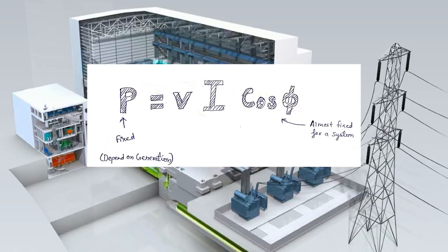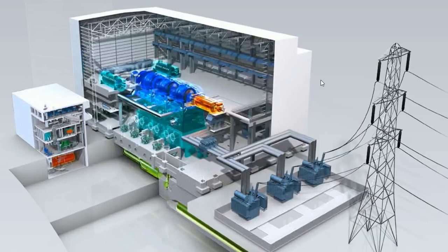Obviously the best choice is higher voltage as much as possible, but high voltage also has limits due to insulation problems. As much as we increase the voltage level, the more insulation discs and greater tower height are required to carry the electrical conductor. However, electrical transformers are used to increase voltage level and decrease the magnitude of current in the transmission line circuit. Let's have some more examples to understand why it is important to increase voltage for long distance transmission.